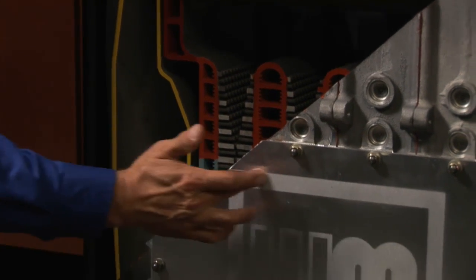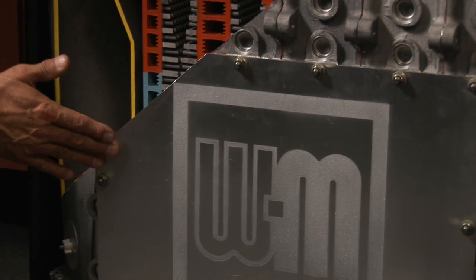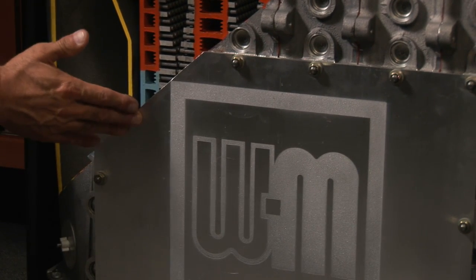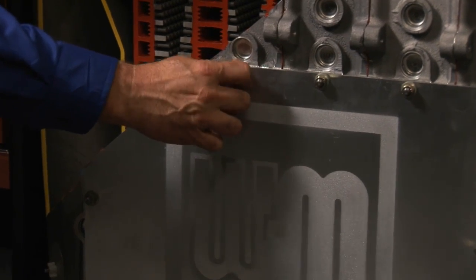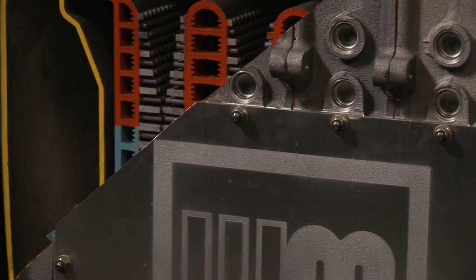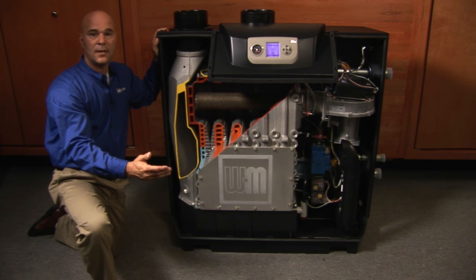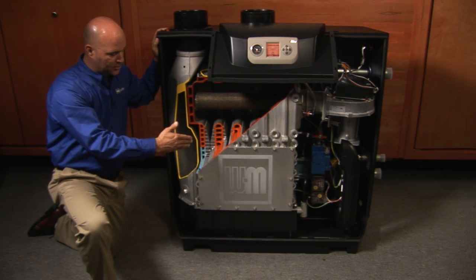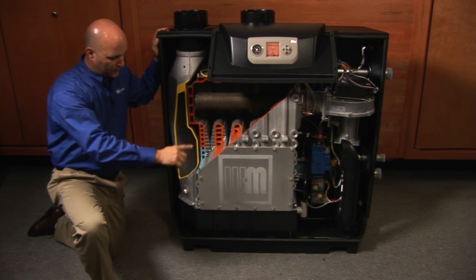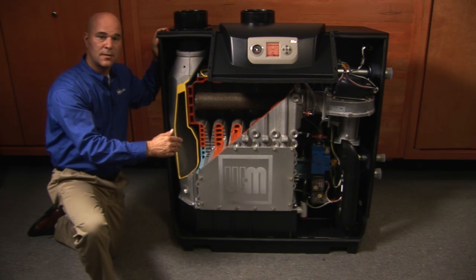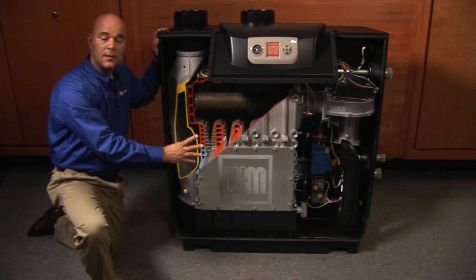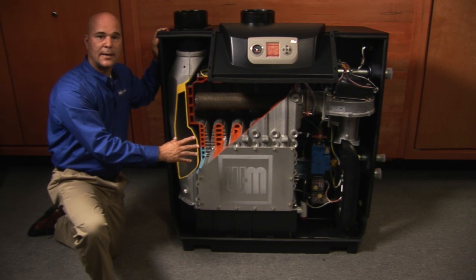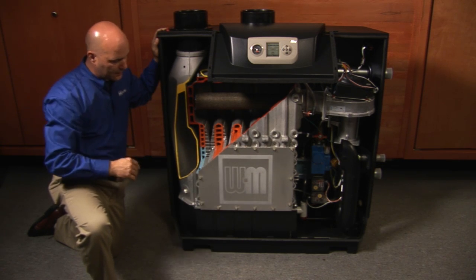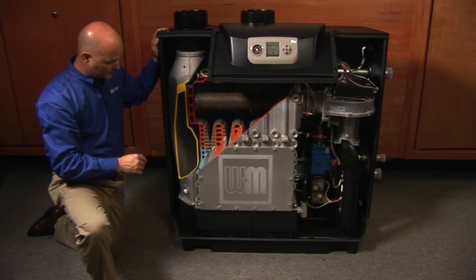This plate right here, this is the clean out plate. This plate will be removed for your annual servicing. You just undo all these nuts, the whole front plate will come off. We have a maintenance kit that you can purchase. It gives you the gasketing material, the high temp silicone. It gives you everything you need to take that cover plate off and put it back on and not have any issues and worry about repairing a gasket or anything.